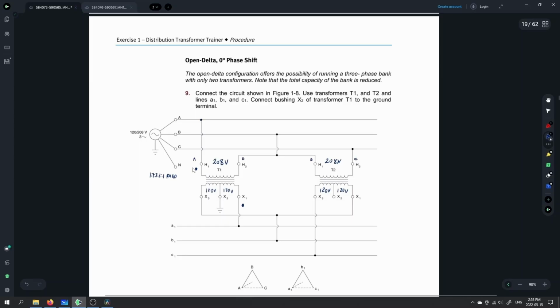H1 is being fed from A, so X1 is feeding A here. So this should be A to B, and then this guy should be B to C. So A down here, X3 is going to B. And then we can see here that X1 is going to B, and finally X3 is going to C. So we should be able to get 3 phase out even though we have 2 transformers here.